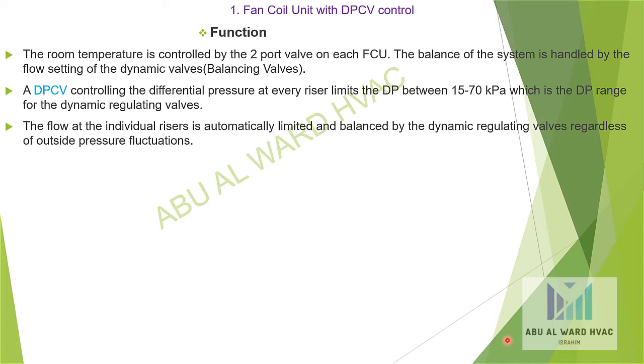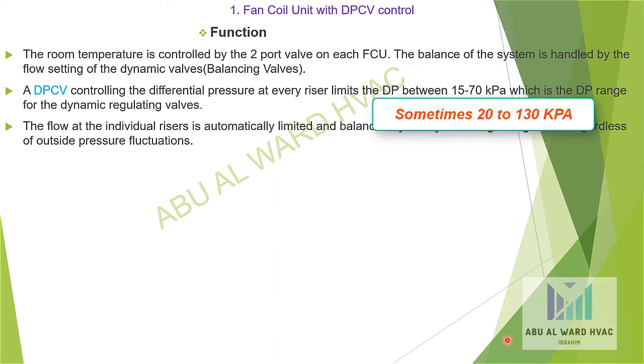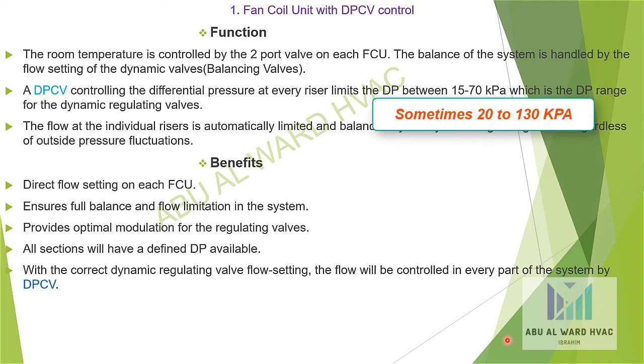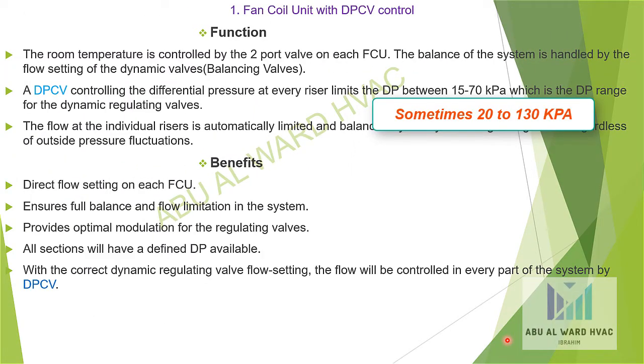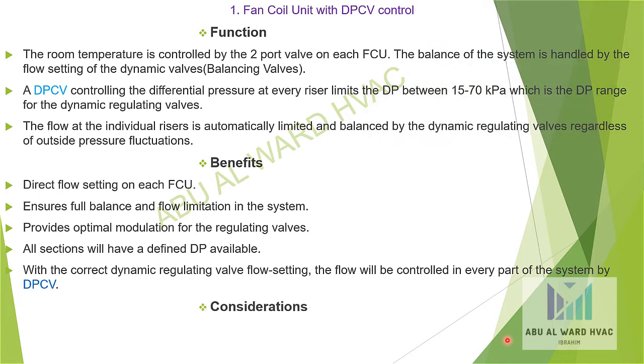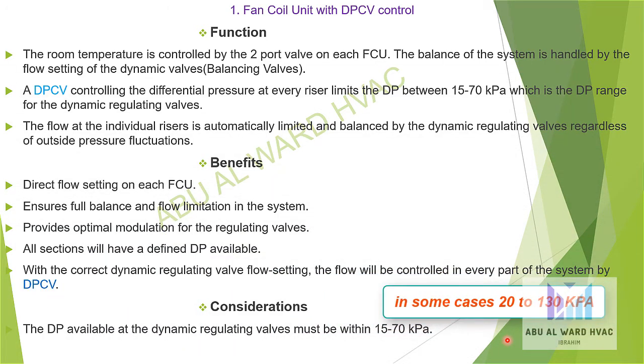A DPCV controlling the differential pressure at every riser limits the DP between 15 to 70 kPa, which is the operating range for the dynamic regulating valves. The flow at individual risers is automatically limited and balanced by the dynamic regulating valves regardless of outside pressure fluctuations. Benefits: direct flow setting on each FCU ensures full balance and flow limitation; optimal modulation for regulating valves; all sections have a defined DP available. Consideration: DP available at the dynamic regulating valves must be within 15 to 70 kPa.